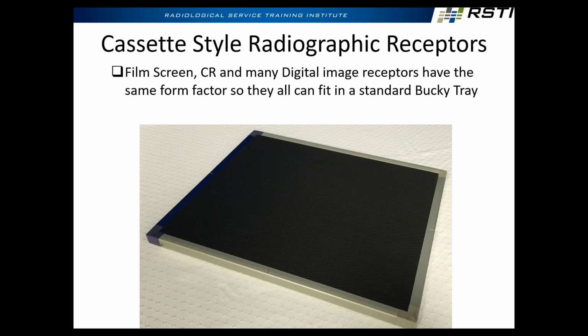Manufacturers will put drop sensors in these and void warranties once they get above a certain amount of drop levels. There's actually an accelerometer built in there, and if it hits certain G's a certain number of times, you can void warranties with that. So yeah, less expensive. It's portable, but the problem is it's portable, and humans are interacting with it, and that can cause a problem. But if you had a rad room with a chest stand and a wall, or a chest stand and a table detector, that increases your cost by easily a couple $100,000. So it can be a very economical method, these portable detectors.